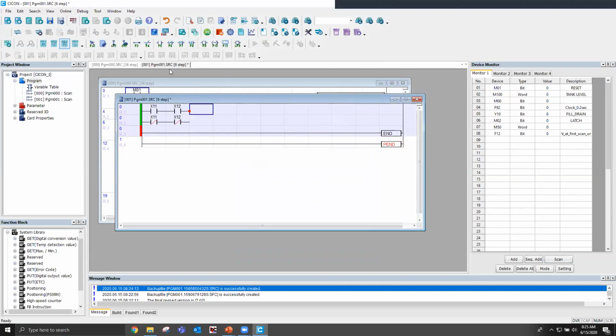See how that was kind of a lot of work? It wasn't really a lot, but it's a minor example of what I'm trying to say - I had to do some processes to do bit comparison, whereas if I made a function block dedicated to this, I'd only have to input two little bits every time and be good to go. So right here it's comparing if x11 and x12 are both on or both off, and if they're both on it commits to the action, and if they're both off it commits to the action too. Then I can make a function block that embeds this function for myself if I want.